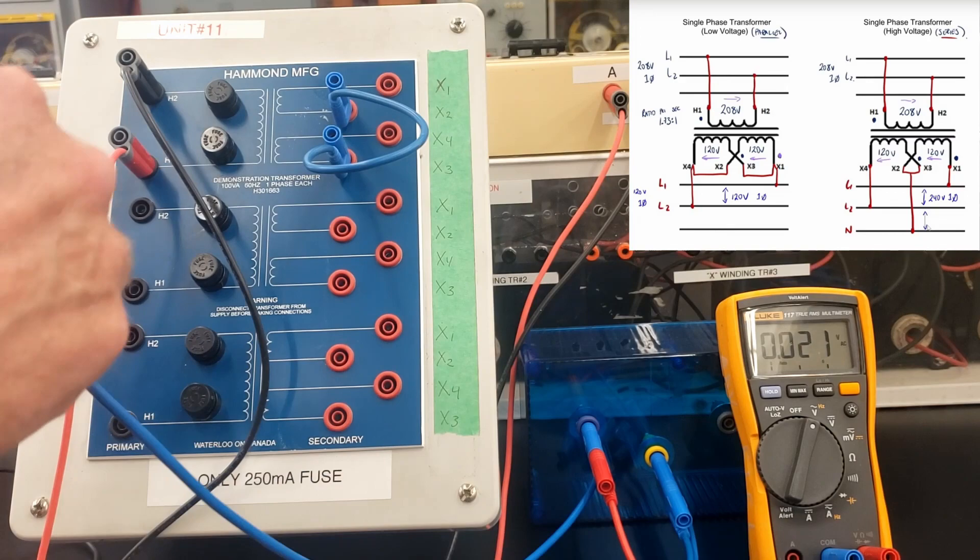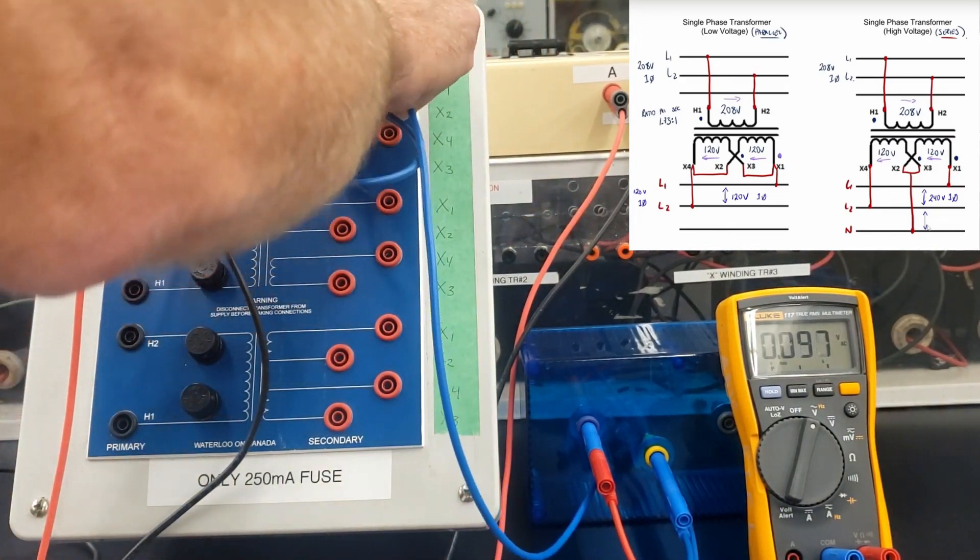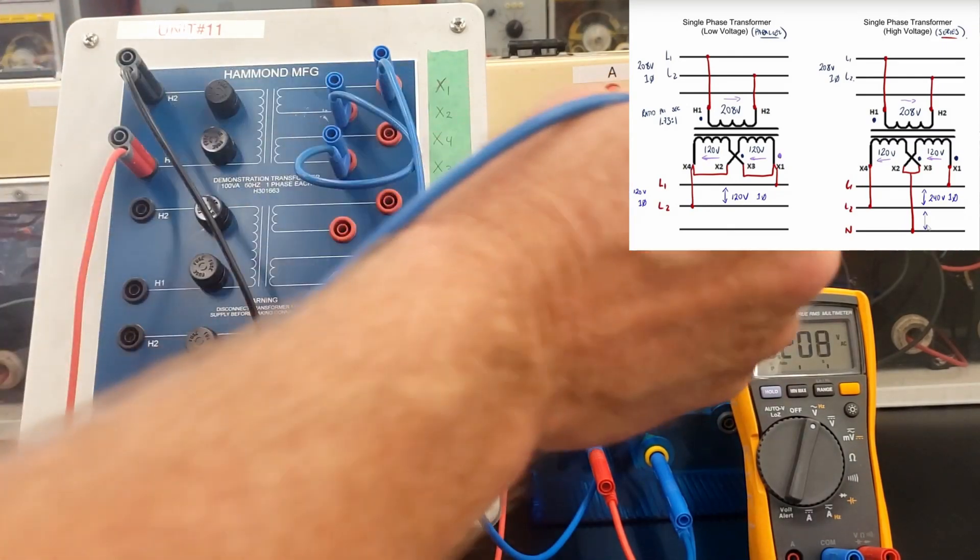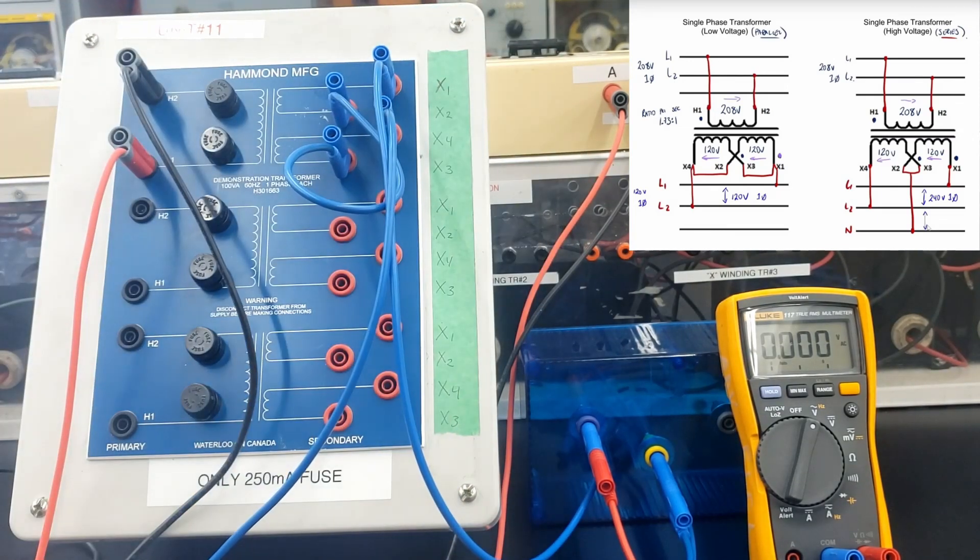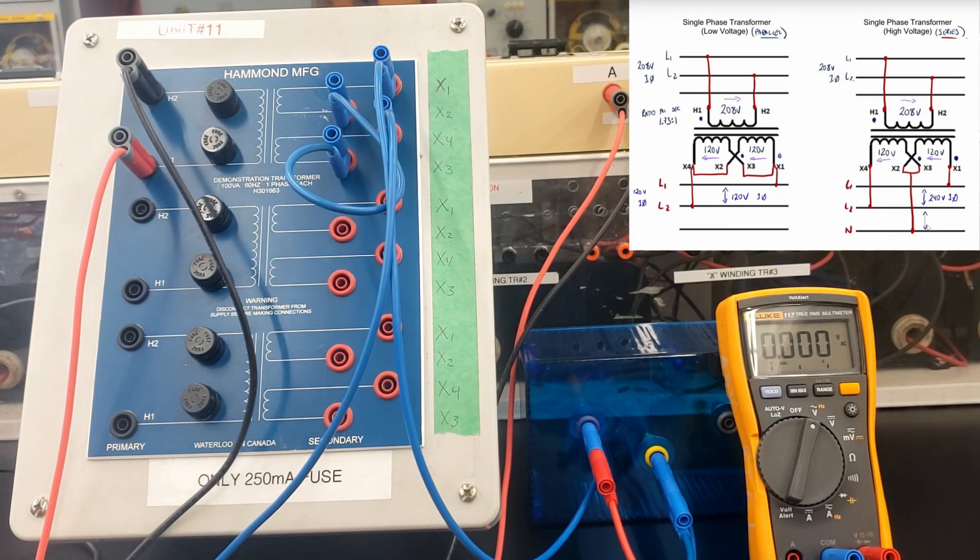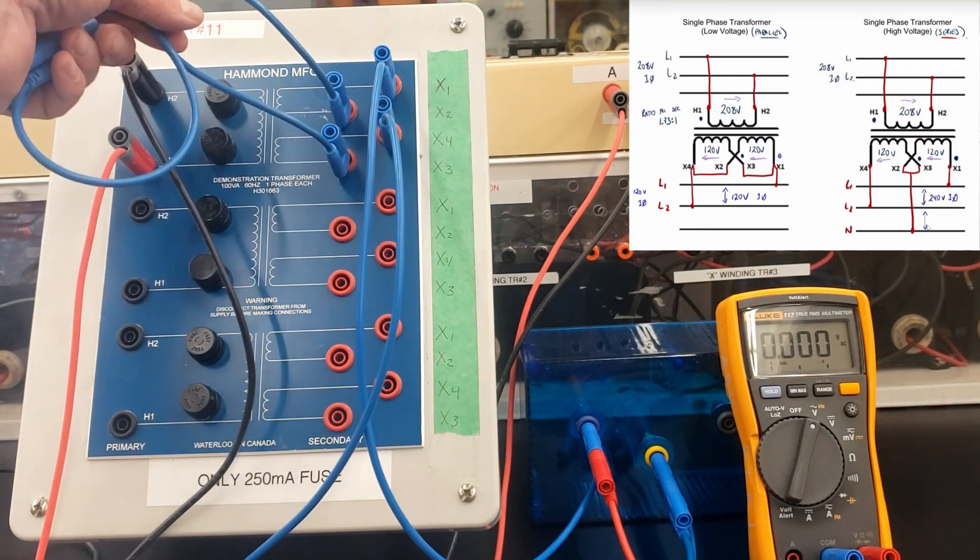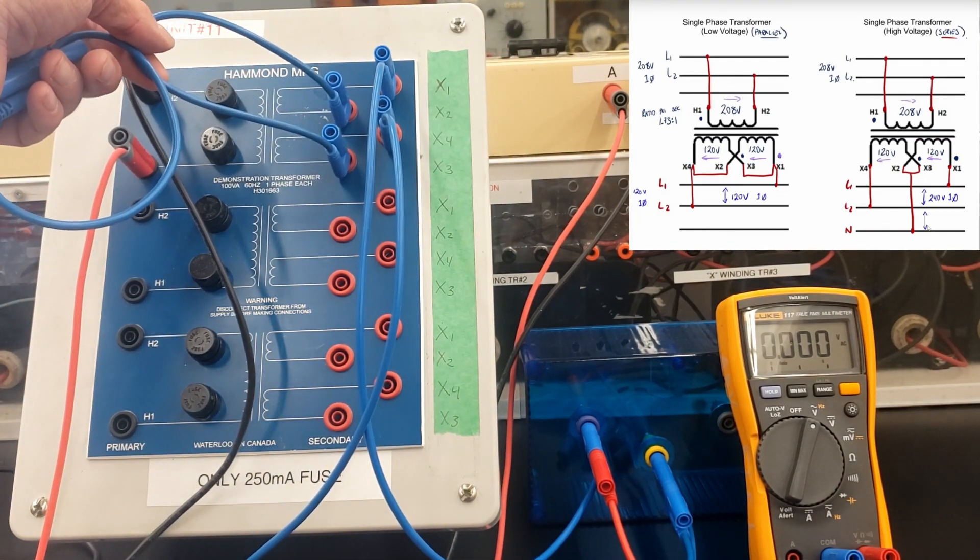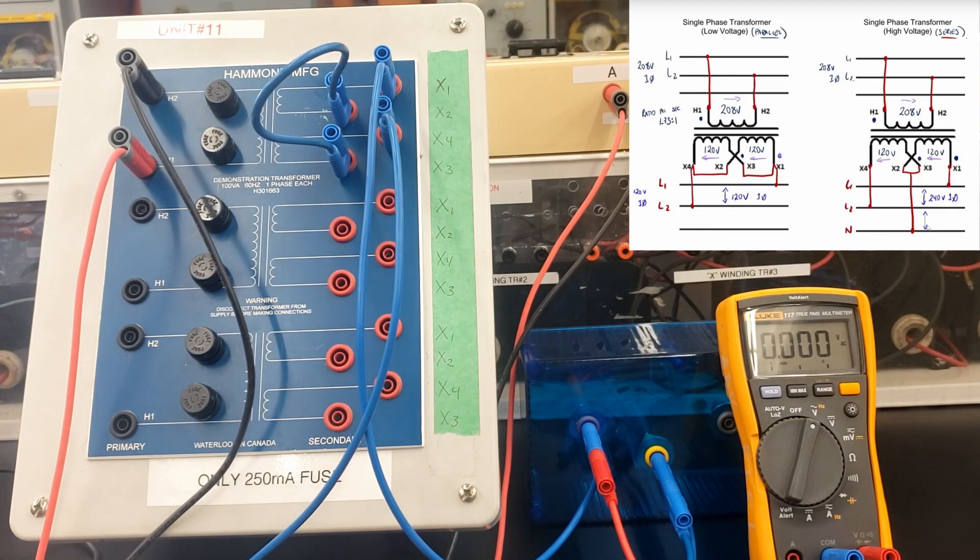The beauty of these transformers is that we can do, because they have two secondary windings, we can do both the low and the high voltage outputs for these guys. Low voltage always means parallel connection. High voltage always means the series connection. Let's check out the voltages here.